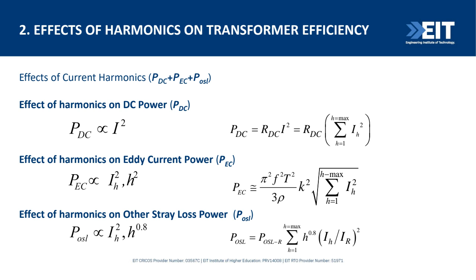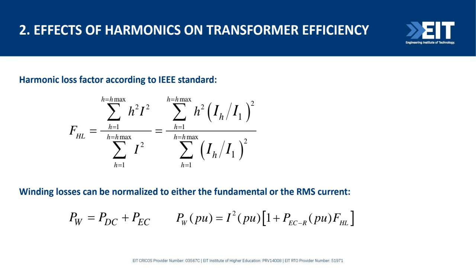So when we look at the IEEE standard, it gives a harmonic loss factor, which is expressed like this here. And we do have winding losses that can be normalized to either the fundamental or the RMS current. So if we normalize the winding losses, we can write it like this expression here, which can be found in the IEEE standards and the IEC standard that I mentioned. We have an almost copy-paste of these formulas in our Australian standards as well.